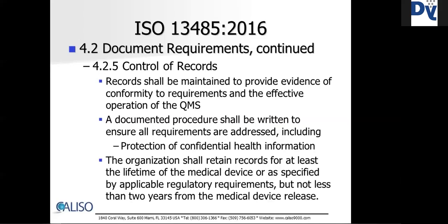The organization shall retain records for at least the lifetime of the medical device or as specified by applicable regulatory requirements, but not less than 2 years from the medical device release. This provides confidence of traceability should there be any kind of problem with the device.